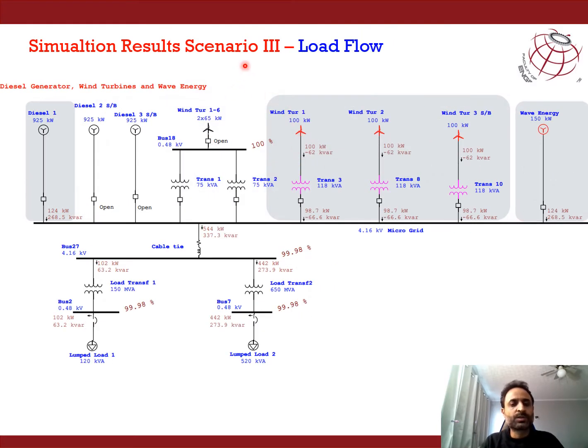The third scenario, which we were able to converge in this paper, was for diesel generator, wind turbine, and wave energy as the generation. So the breakers for the diesel, the wind turbines, and this new wave energy generator have been switched on, and then the results converged. You can see that the generation of the diesel plant has reduced significantly as compared to the first two scenarios. Now the major part of the load is being fed by the wind turbines as well as the wave energy generators, and the reactive power required by the wind turbines as well as the load is shared by the diesel generator and the wave energy generator, because we will have a synchronous generator in the wave energy generation. In this case also, we are able to maintain a healthy voltage on the load bus, and the 102 kilowatt and 442 kilowatt active power is being met majorly by the renewable generation in this scenario.